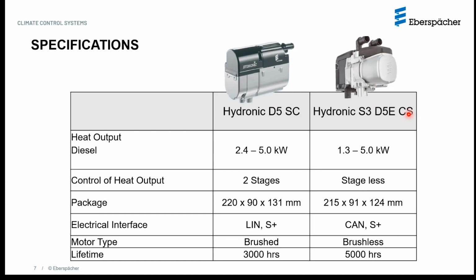So now let's take a look at the specifications. As we know, the maximum output between both the first generation and the third generation still remains exactly the same, no change whatsoever. It's still 5 kilowatt or 17,000 BTU. The minimum output, however, has been tweaked. So you can see initially in the first generation, we had a minimum of 2.4 kilowatt. That's been dropped to 1.3. And the reason to do that is to extend the running time of the heater without it having to restart. As you know, the most common failure point is usually when the unit tries to start and it's not able to start and it fails.